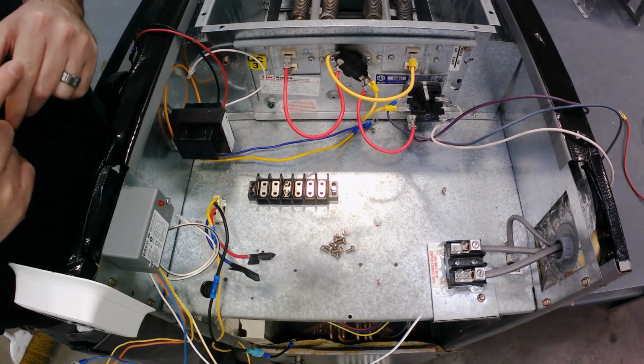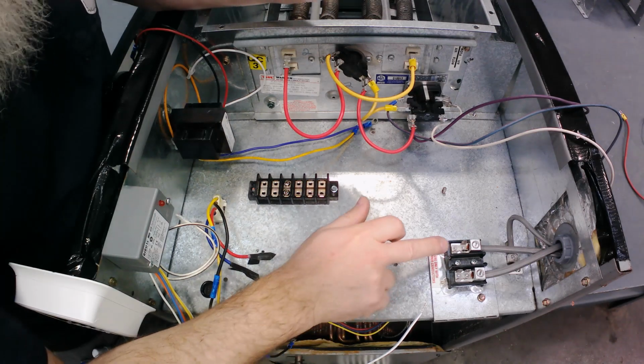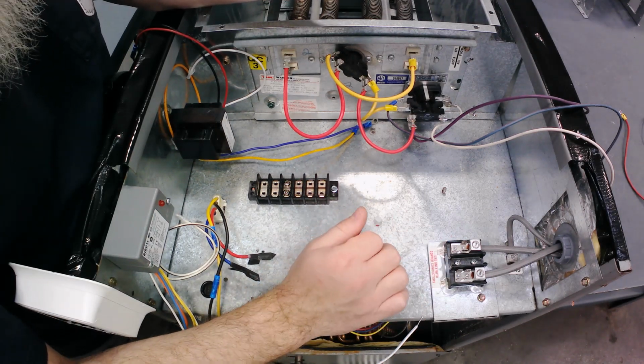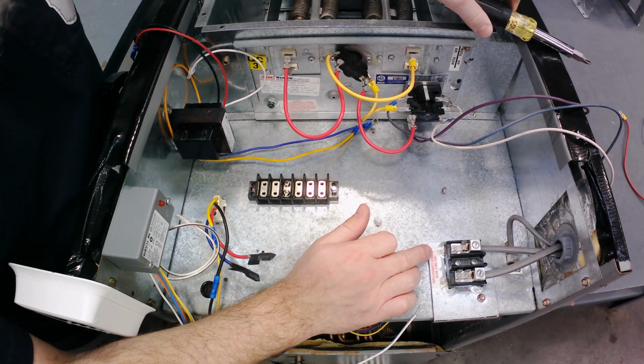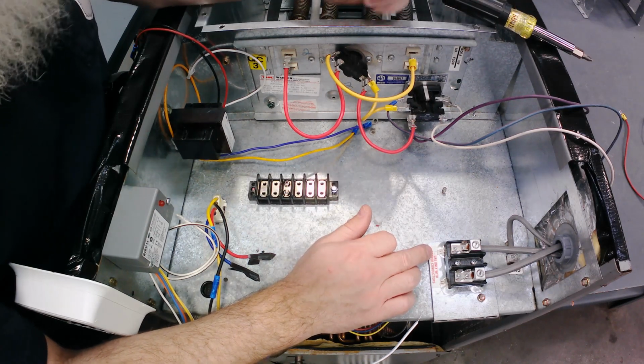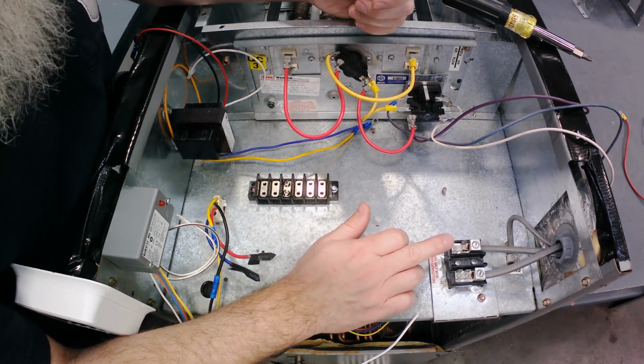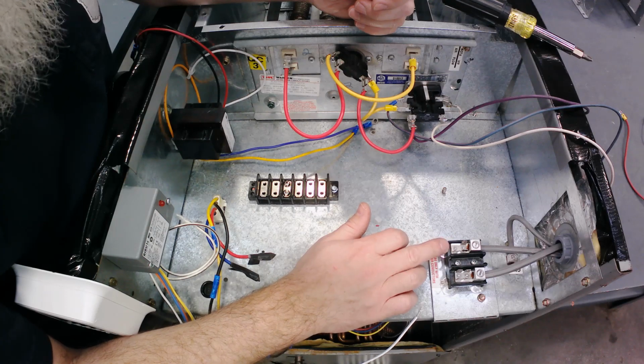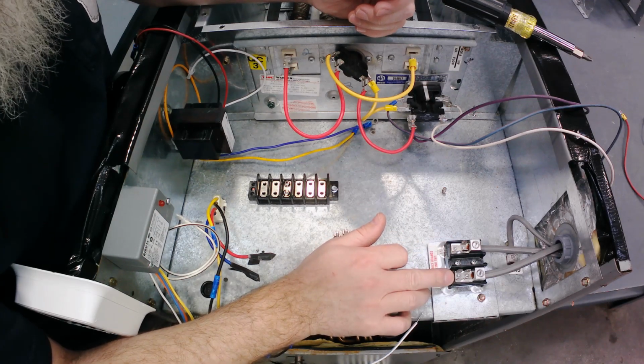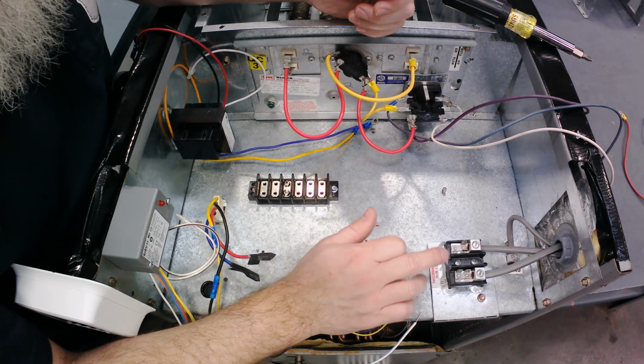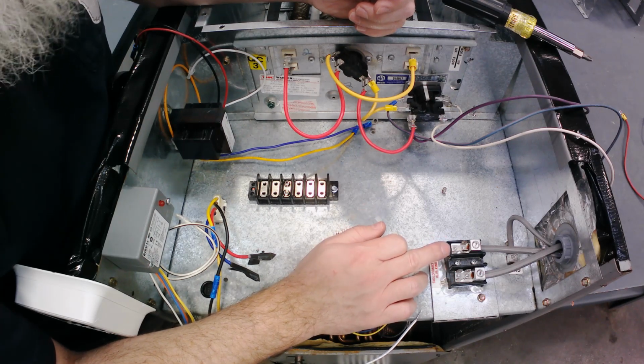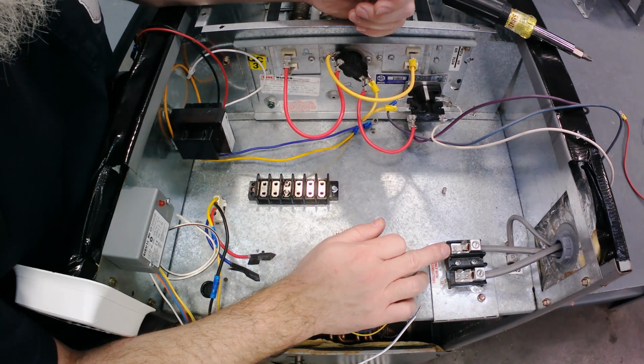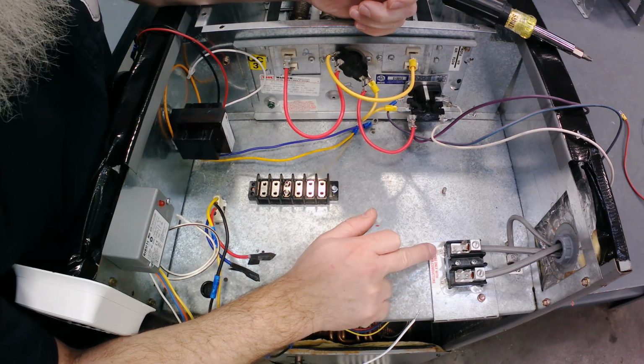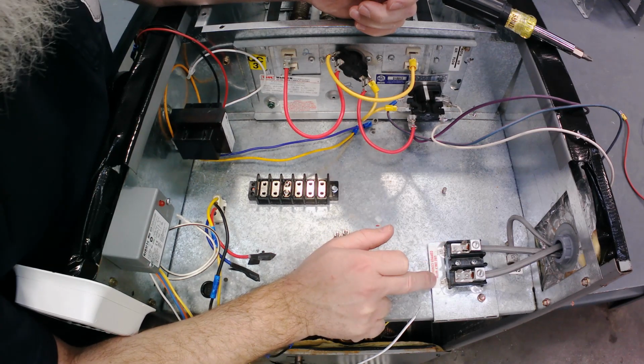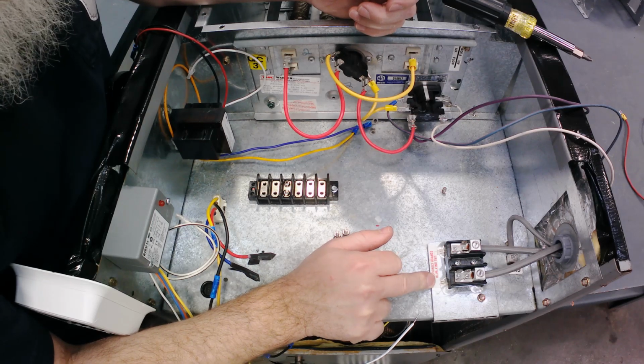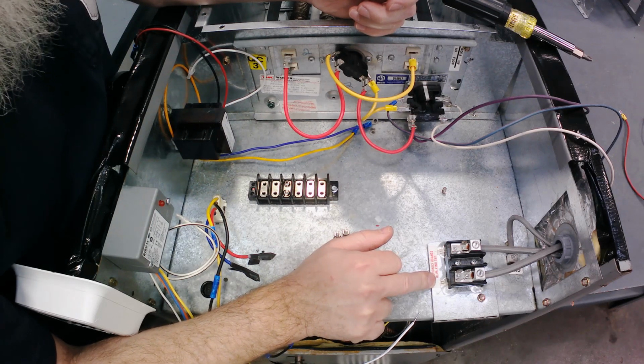We're basically starting from scratch, like I said. So we've got our terminal block right here, and if you've listened to anything I've said before, the way I think about things - in a 208/240 system you have L1 and L2, we have no neutral. When you're starting from scratch, it doesn't matter which one you call what. They've labeled L1 as the upper one as you're looking at it, and L2 as the lower one, but really it depends on the first circuit that you run.